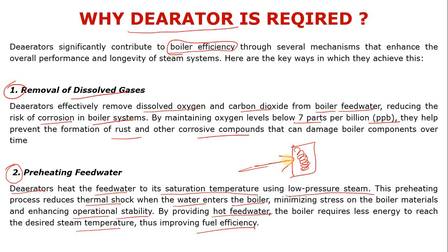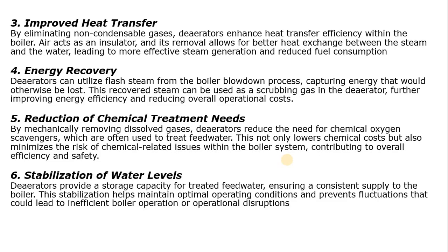Third, de-aerators improve heat transfer. By eliminating non-condensable gases, de-aerators enhance heat transfer efficiency within the boiler. Air acts as an insulator, and its removal allows for better heat exchange between the steam and the water, leading to more effective steam generation and reduced fuel consumption. Fourth is energy recovery — de-aerators can utilize flash steam from the boiler blowdown process, capturing energy that would otherwise be lost.